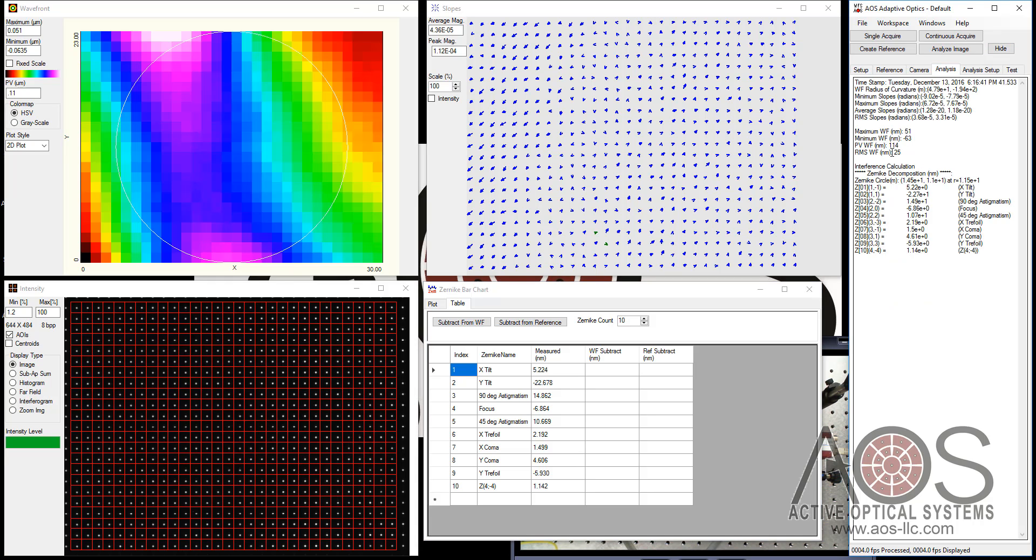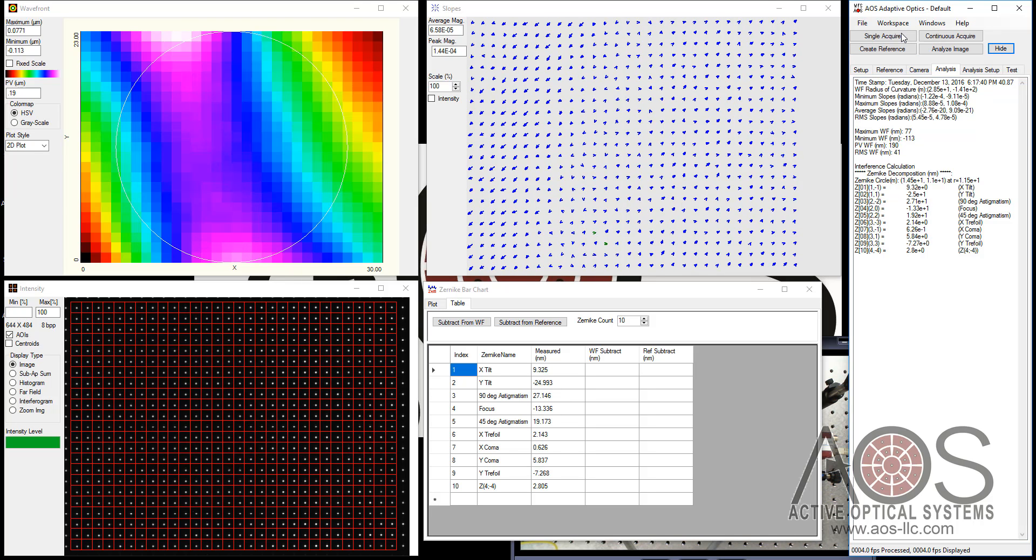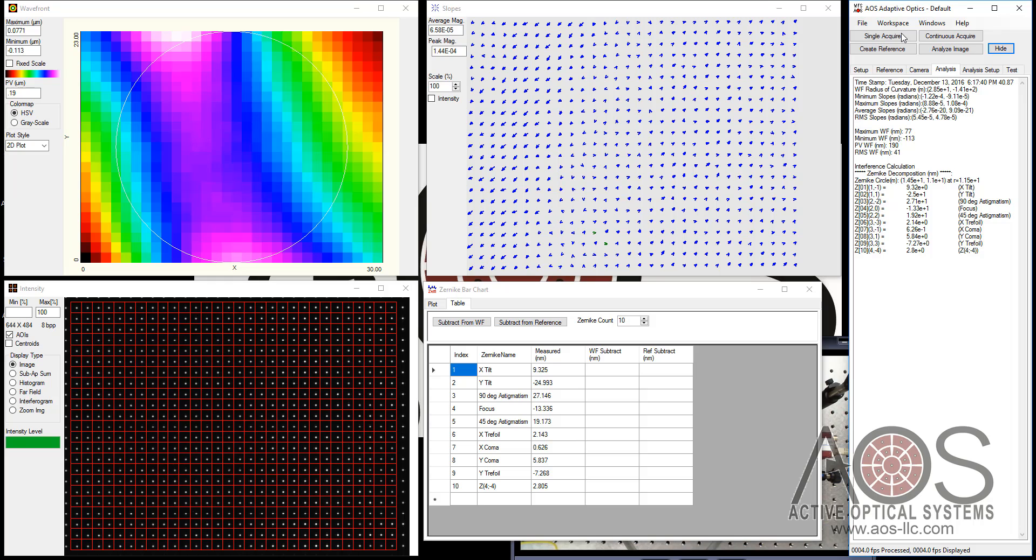This tells me a little bit about what I'm seeing as far as noise goes. I can go in here and take a look. I'm at about 25 nanometers RMS for this. 36, 42. A lot of this noise I think is coming from the blower that we have on the table, the HEPA filters we have on the table. So I'm going to reach up here and turn these HEPA filters off and see if we get a little better noise performance by turning that HEPA filter off.